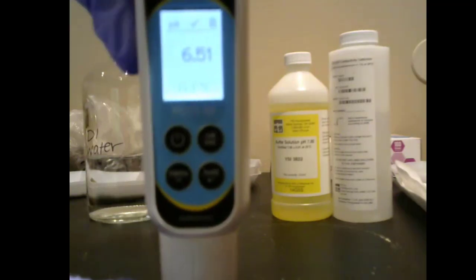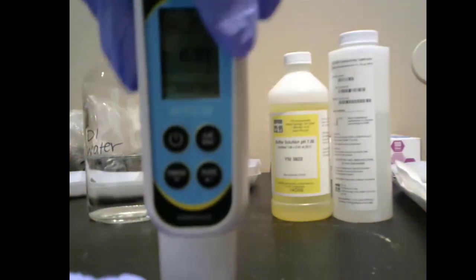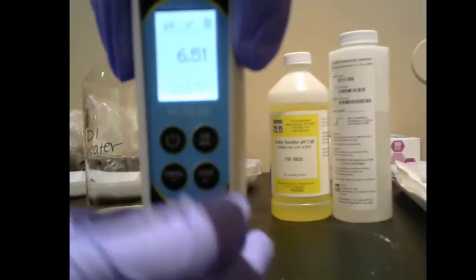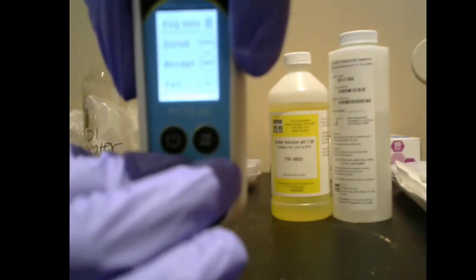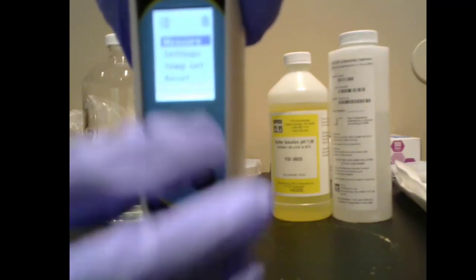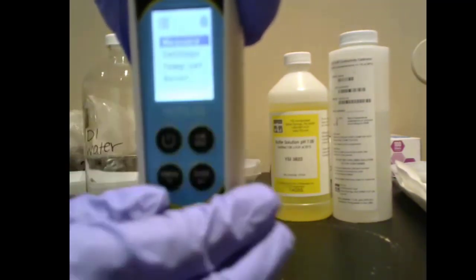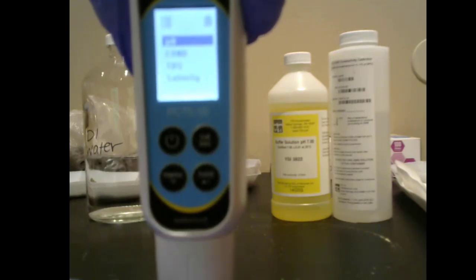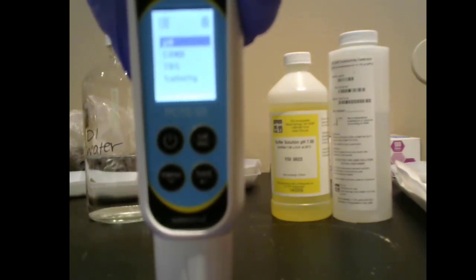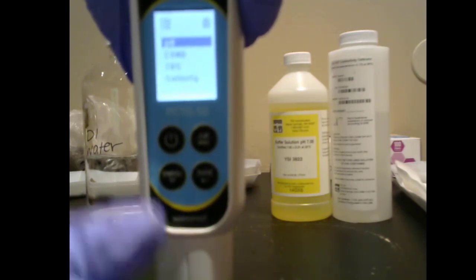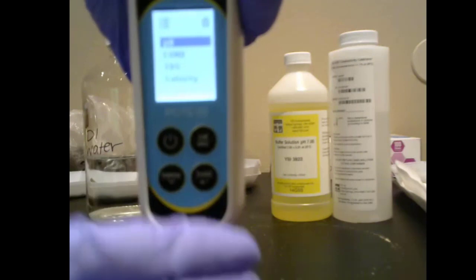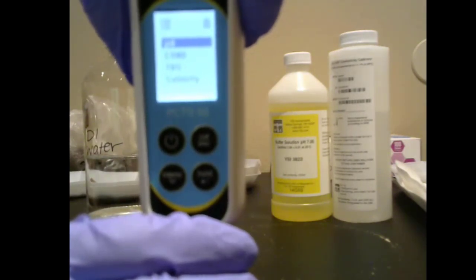Okay, so we need to change this from pH to conductivity to do our conductivity spot check. So what you need to do is go into the menu, and you get this first screen telling you how to use these buttons within the menu. You use menu to scroll, hold to select, and cal to escape. Now we are inside the menu. It says measurements, settings, temperature set, and reset. We want measurements, so we're going to push hold to select. Now you can see there's 4 measurements we can choose from. They are pH, conductivity, TDS, and salinity. Remember, we're only measuring pH and conductivity, then we're calculating TDS and salinity from some mathematical or empirical algorithms.